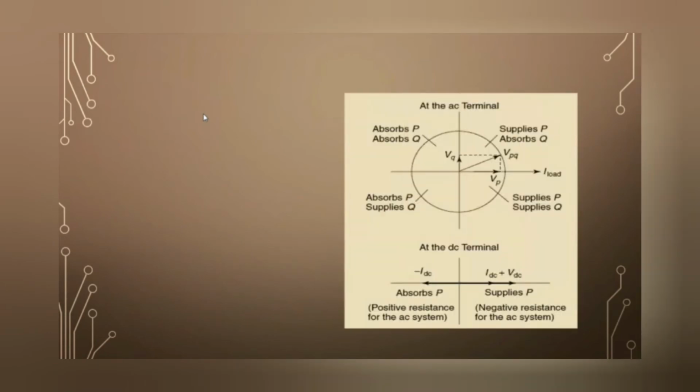So the SSSC is more beneficial compared to the TCSC because of its ability to modulate not only the line reactance but also the line resistance in conjunction with the power swings, thereby imparting enhanced damping to the generators that contribute to the power oscillation.